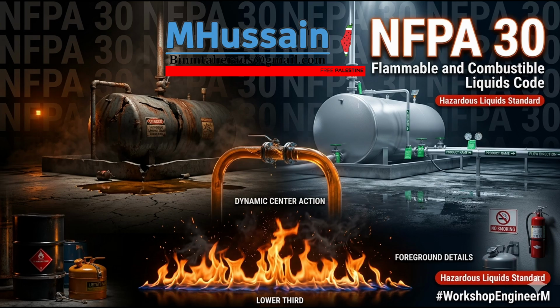It prevents the internal temperature from reaching the boiling points of the solvents inside, which would cause the containers to burst and add fuel to the main fire. The code also says the joints have to be riveted, welded, or thermally tight. You can't just use screws, right? Because they'd warp and pull out in a fire. Right, compromising the air gap. And there's this detail about the base. The door sill has to be raised at least 2 inches above the bottom inner surface. That's a built-in dike. If someone drops a glass bottle of reagent, that 2-inch sill keeps the liquid entirely contained inside the cabinet footprint. So it doesn't creep out under the door and find a spark 50 feet away?